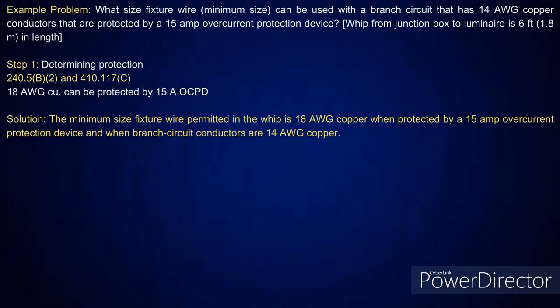This is just showing size and fixture wires and how they can be used with a branch circuit that has number 14 conductors protected by a 15 amp overcurrent device. And we have a fixture wire from the junction box to the luminaire. Now, that junction box right there, you can call it a junction box, but it's also an outlet. Do you know why they permit you to use number 18 or number 20 gauge fixture wire to the junction box? Because it's already been listed and labeled and sized for that size wire. They know how much amperage it's pulling, because it's technically a tap.